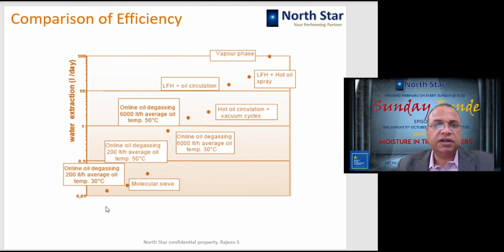So if we look at the capacity, I mean efficiency, that is water extracted in terms of liters per day, then vapor phase system is excellent, which can draw around 100 liters of water in a day. But vapor phase drying is not easy to do at site, although now there is one mobile vapor phase drying system available in India, in Pune. So that system can be taken to the site near the transformer, and there the vapor phase drying can be performed. But it is a very costly approach.